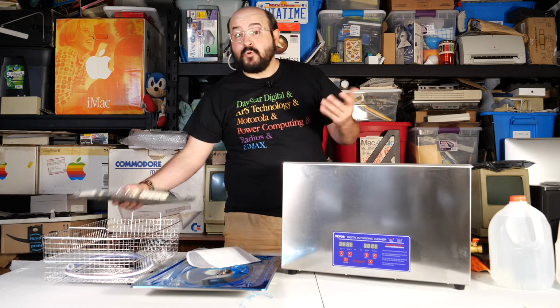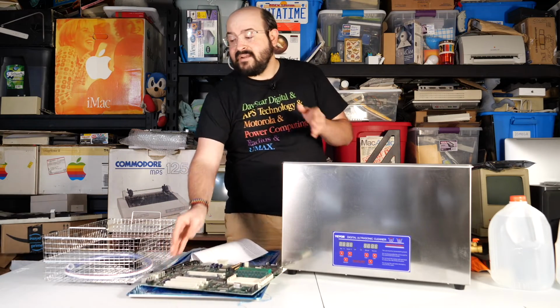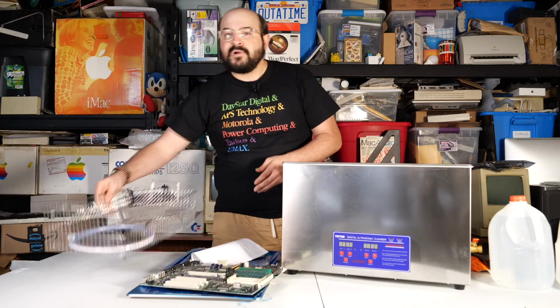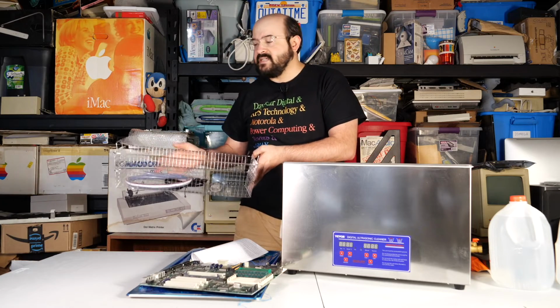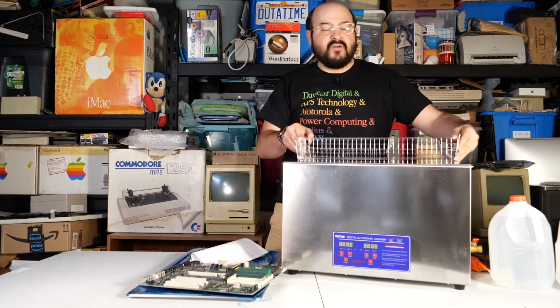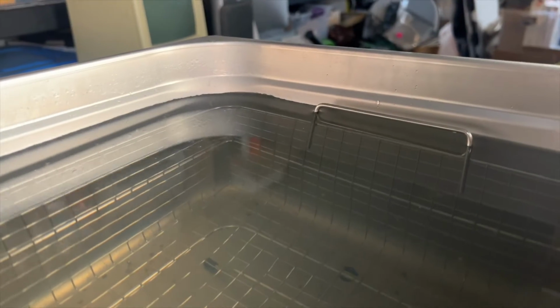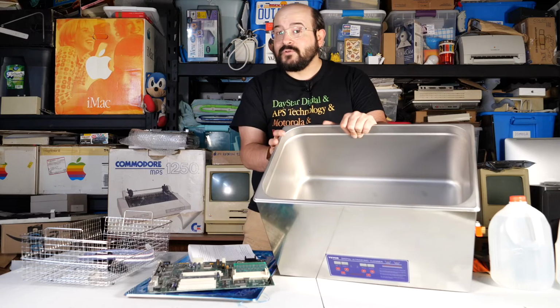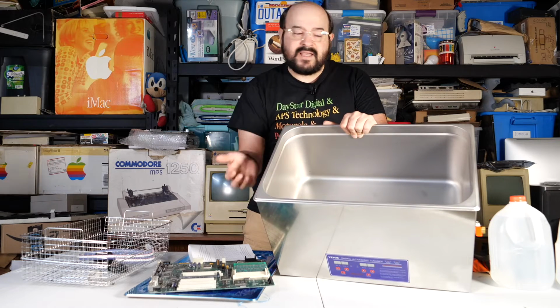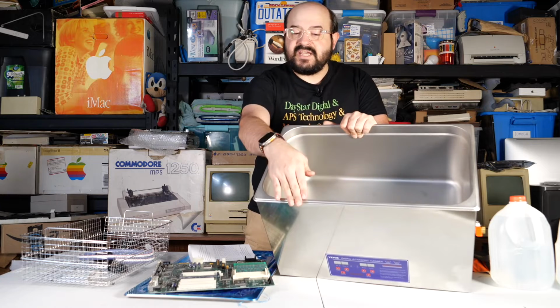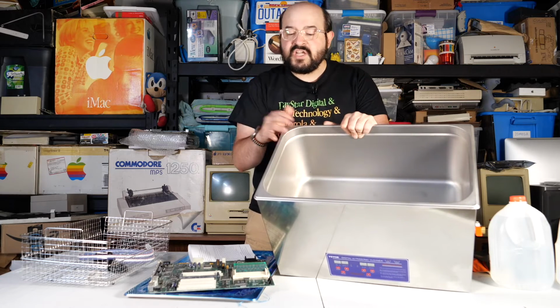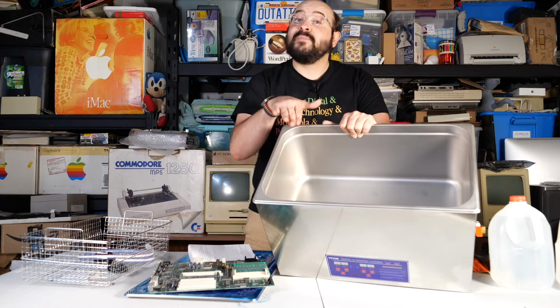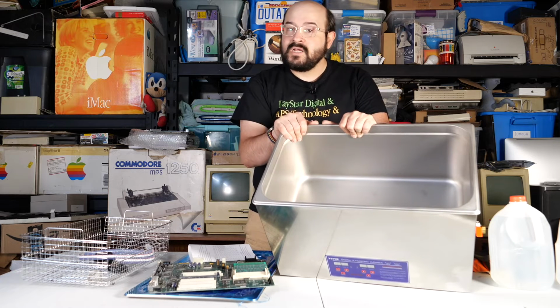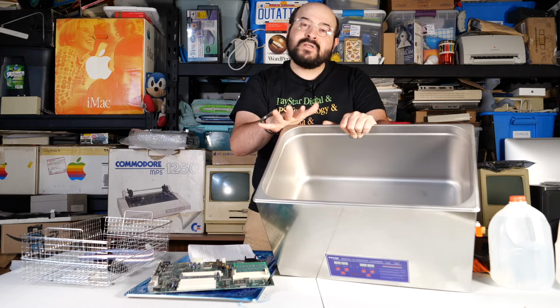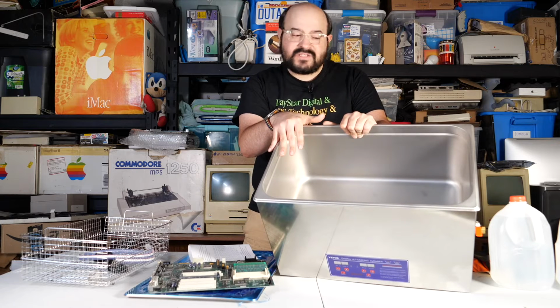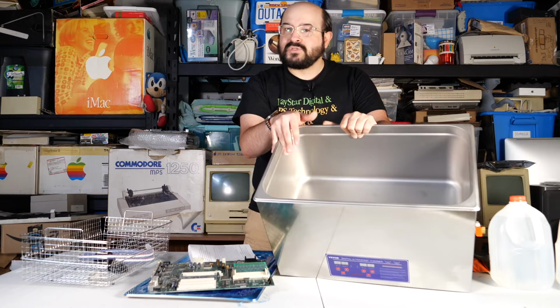Sometimes the product manual or website will list the tank size and the basket size separately. What you probably want to do is go for the basket size, as that's a pretty good estimate of what you could fit inside the tank, since the basket is fully submerged. A lot of ultrasonic cleaning tanks are rounded, so if it says this is, say, 12 inches by 17 inches, you have to take into consideration there may be tapered edges or rounded corners. So if you have something that's going to press against those capacity limits, you may want to consider getting a larger ultrasonic cleaner.